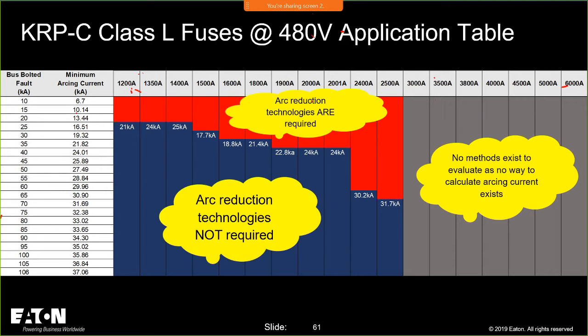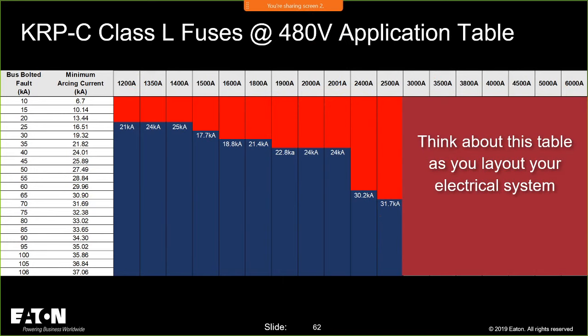As my fuse sizes go up, the bolted fault current I need gets larger. At 480 volts, right around the 3,000 amp fuse range is where I start to need more than 106,000 amps of bolted fault current to get into the instantaneous region, or a 0.07 second clearing time for that fuse. Now, the question is, what do I do about that region? I have an inspector who wants to see an arcing current.